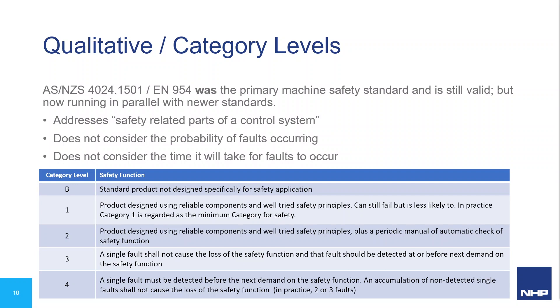The qualitative standard is based on safety categories — there are five of them, between Category B and Category 4. The standard is AS/NZS 4024 Part 1501, which until the last 10 years or so was the primary machine safety standard in Australia. It was recently reviewed and reconfirmed, meaning it's still perfectly valid. What makes this qualitative is that it's based around the behaviour of a safety control system and how it responds to faults — the quality of the system.